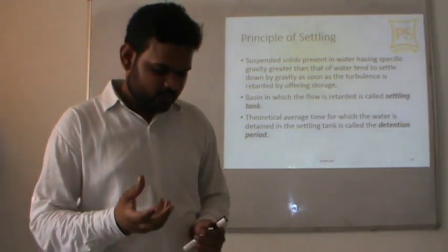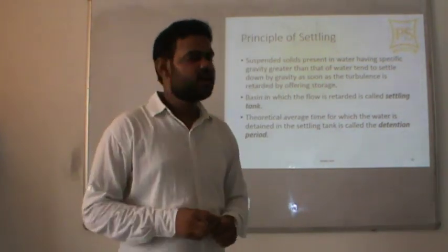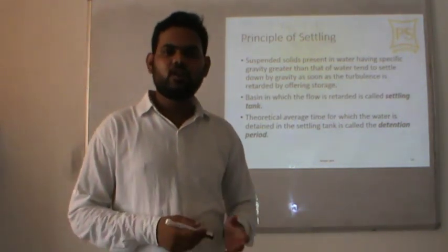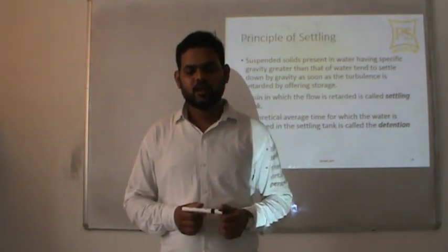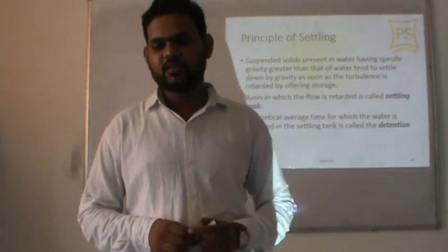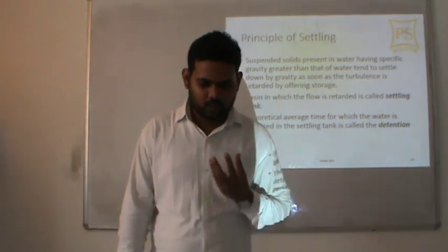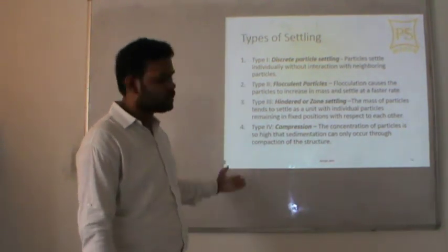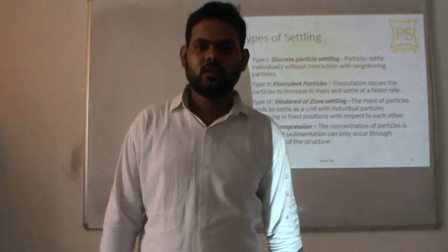Storage is provided by letting water rest. The basin in which flow is retarded is called a settling tank, also referred to as a sedimentation tank. The average time for which water is detained in the settling tank is called the detention period — it is the time for which a particular amount of water is stored in that particular tank. There are four kinds of settling.